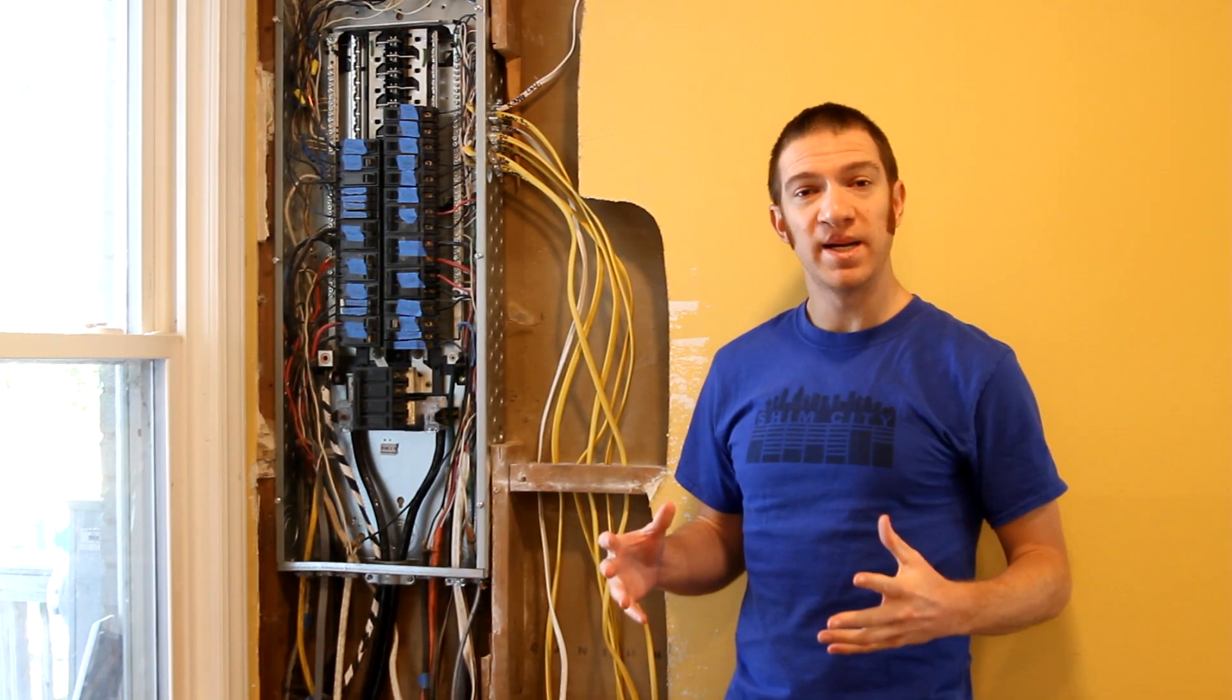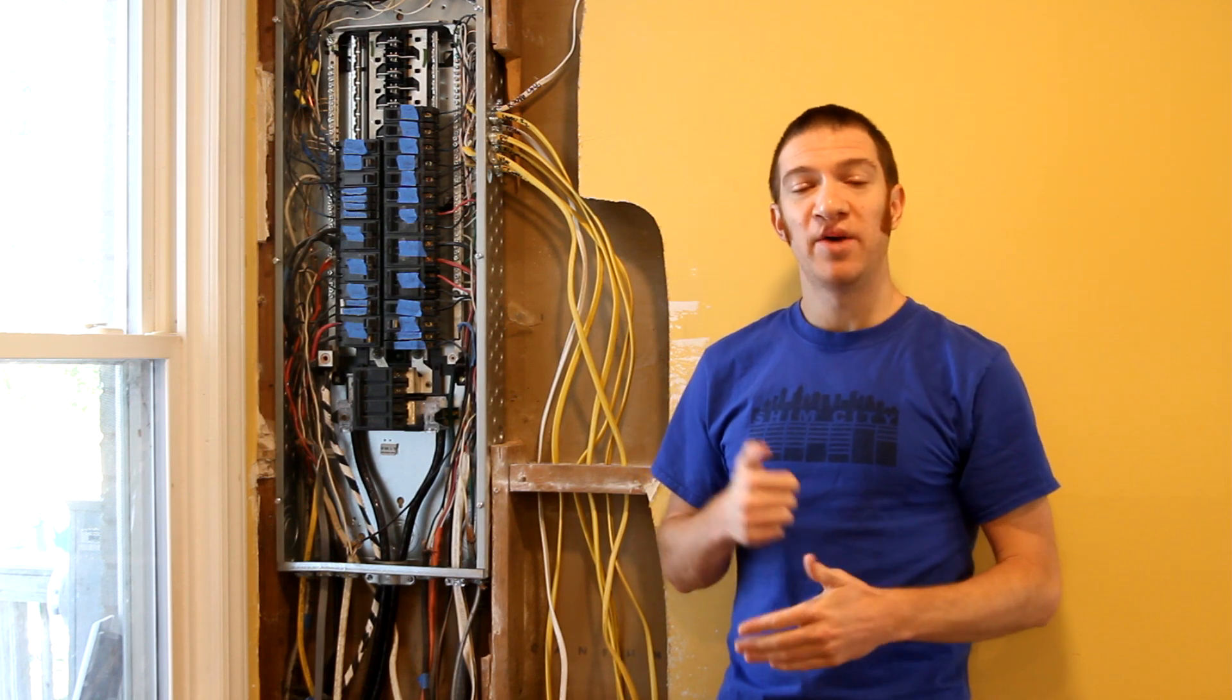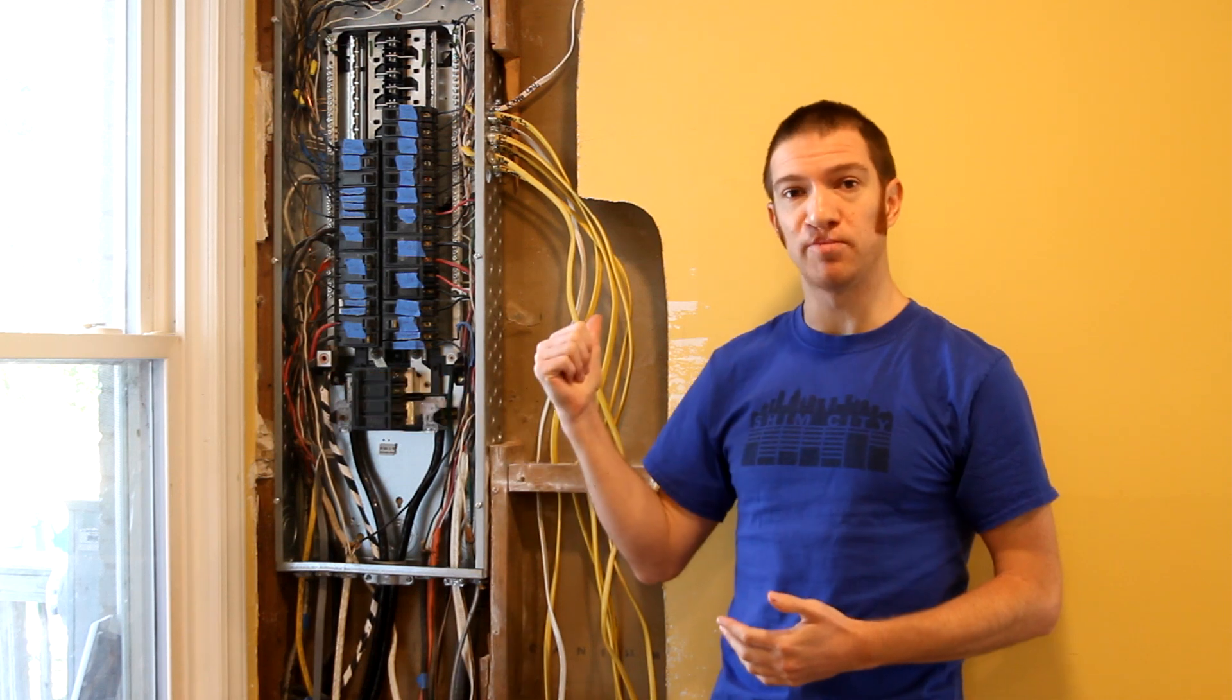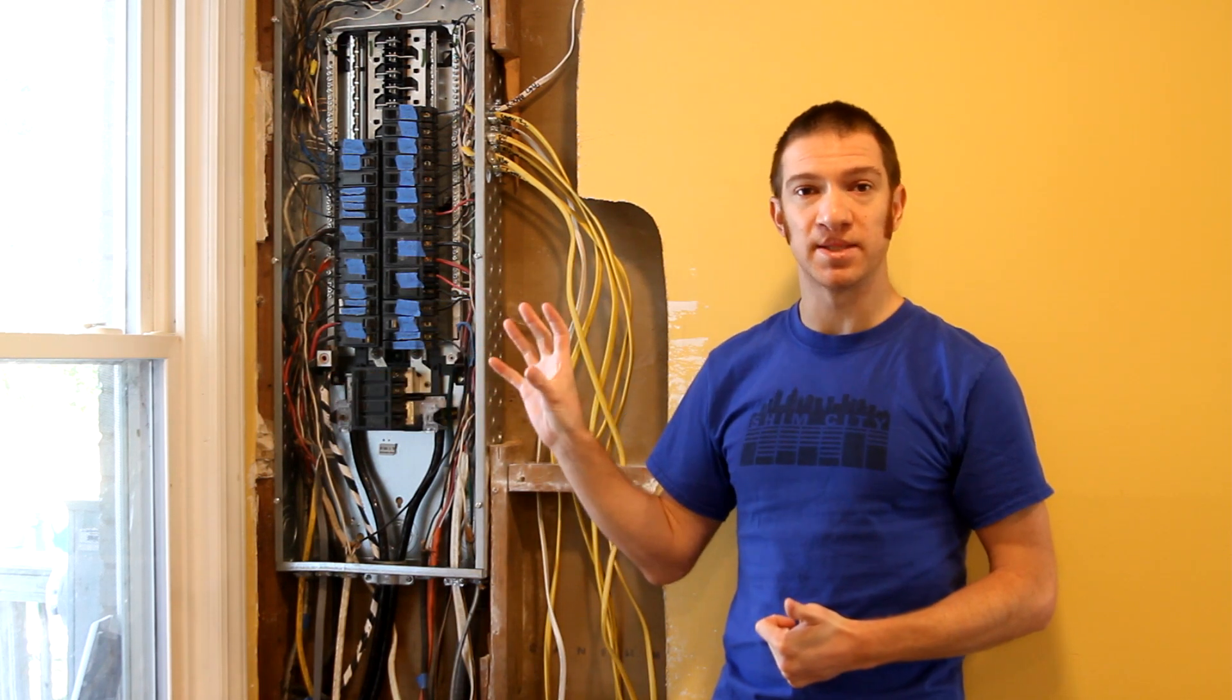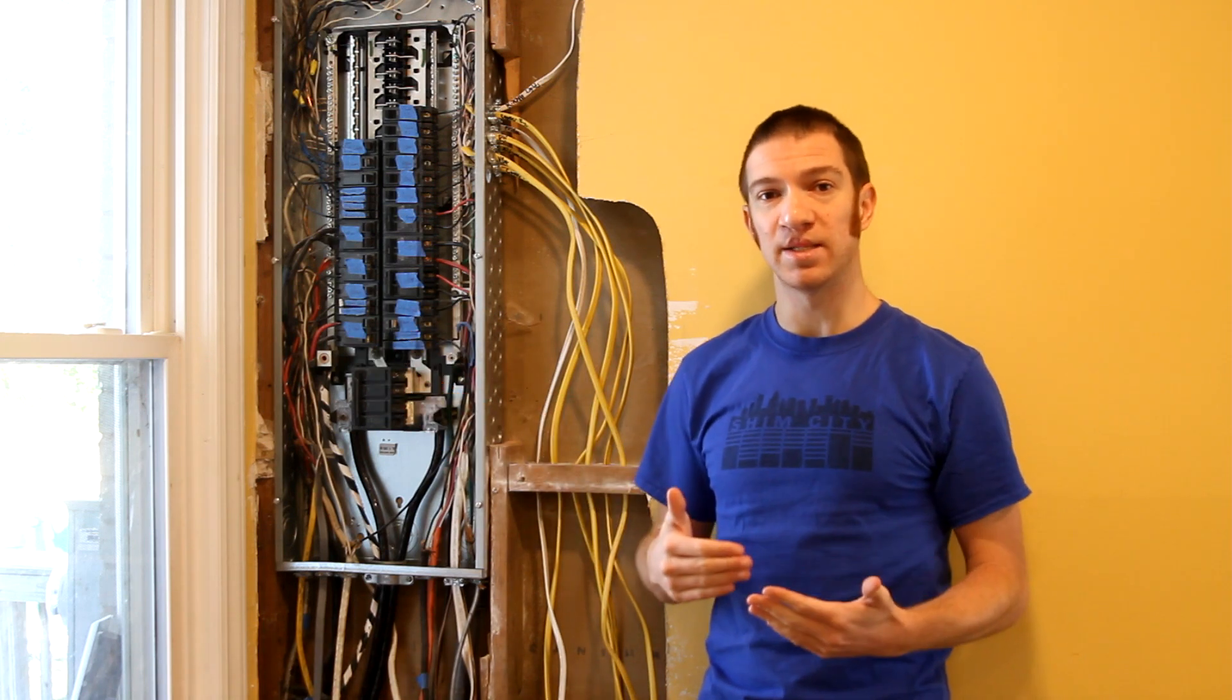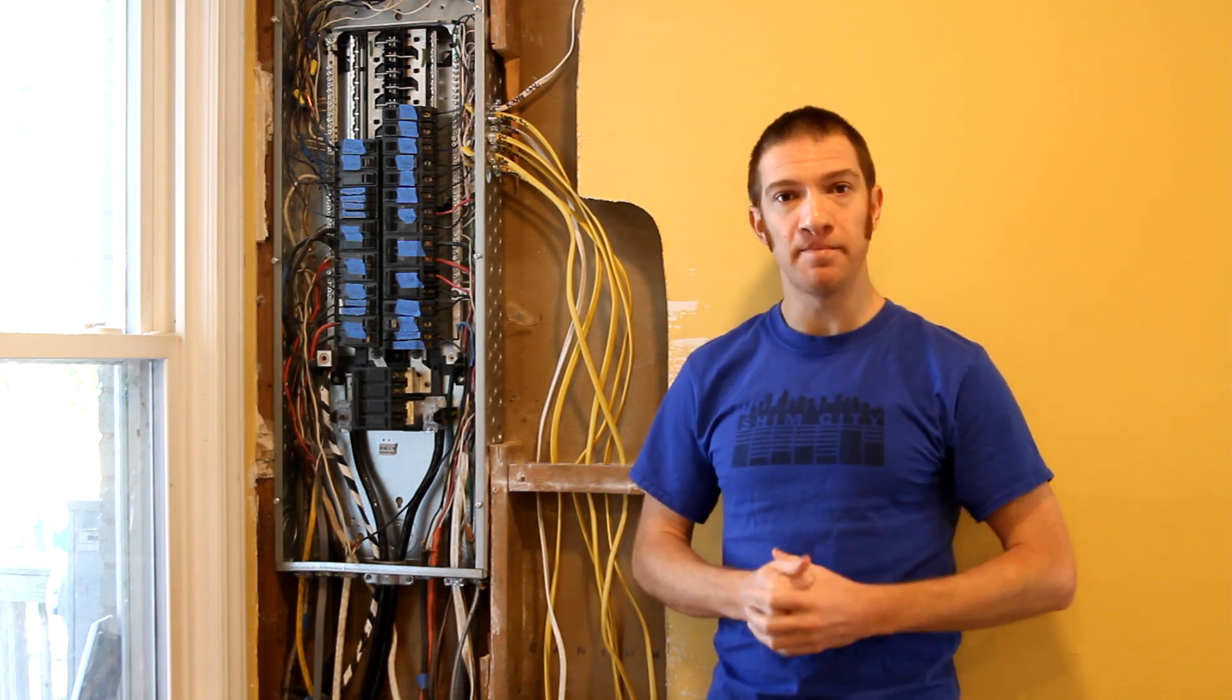If your plans involve increasing the amperage capacity of your main panel, then you have the extra consideration of making sure that your main service lines are up to the capacity of your new panel. You'll contact your power company and they'll have to make that change themselves since those lines belong to the city. Hopefully you can coordinate that change out with the change out of your main panel so you only have the power shut off one time.